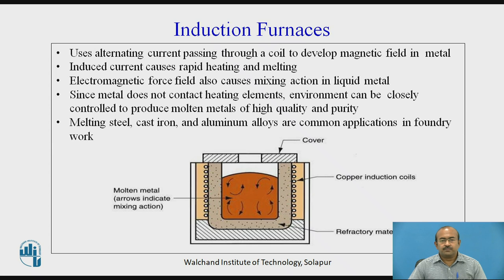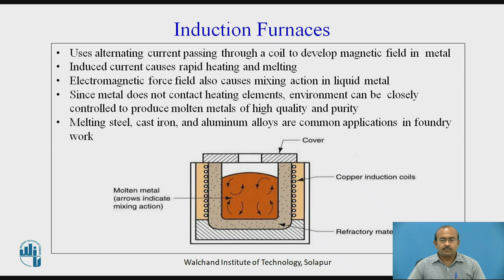The induction furnace uses alternating current passing through a coil to develop a magnetic field in a metal. The induced current causes rapid heating and melting. The electromagnetic force field also causes a mixing action in liquid metal. Since the metal does not contact the heating element, the environment can be closely controlled to produce molten metal of high quality and purity. Melting steel, cast iron, and aluminum alloys are common applications in foundry work. The figure shown on the screen is self-explanatory for the induction furnace.